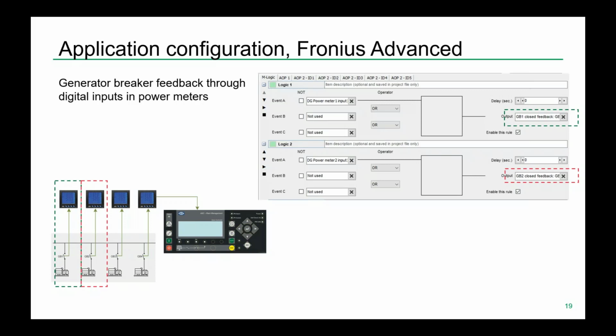So the idea is in mLogic you just set up, for instance, in logic 1, diesel generator power meter 1. That means generator breaker 1 is closed. And the red square means diesel generator power meter number 2, the second power meter. This means generator 2 is closed, and so forth. So this way, in an easier way, just with a Modbus cable from the basement to the roof, you get to know all about generator power and position status.